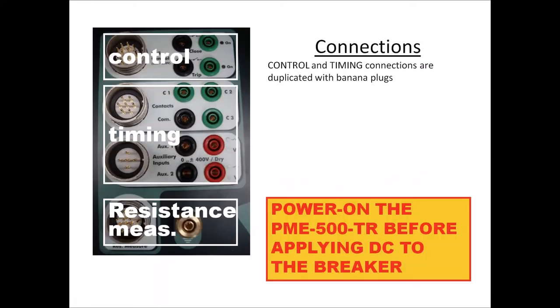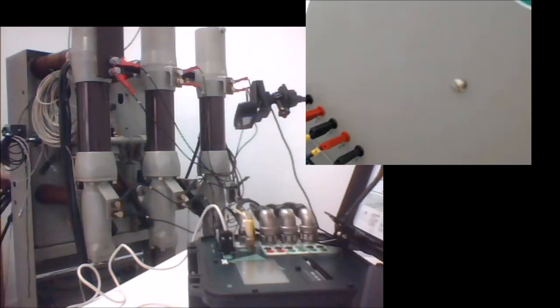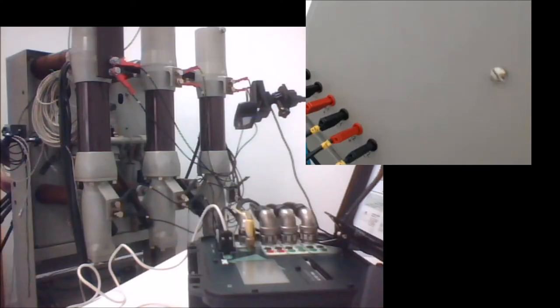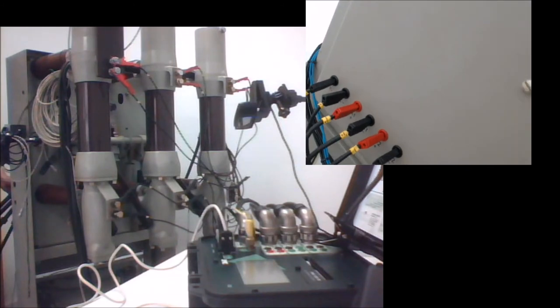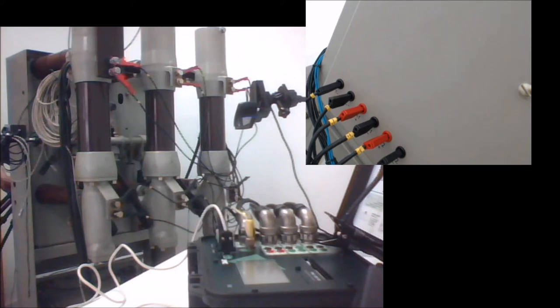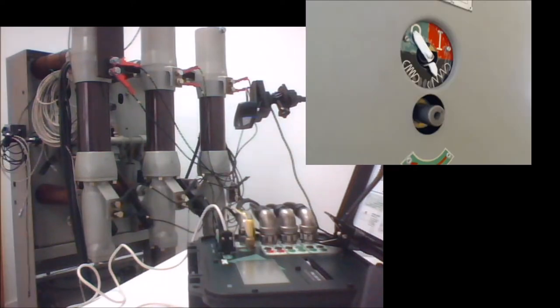The control multi-connector here is connected to the operation coils in the breaker. You can see a group of connections, two of which correspond to the close and open coils in the breaker. Now I will start showing you the basic operation — how we set up the test and prepare the instrument to perform the test we want to do.